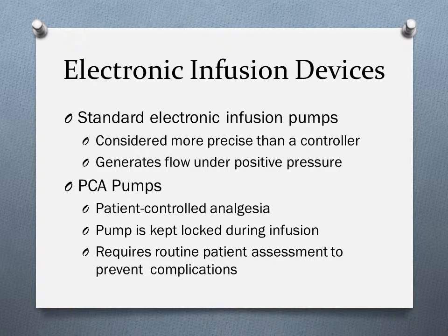Again, with PCA pumps, these are programmable for continuous infusion, bolus infusions, or both. They have a remote control mechanism where the patient can deliver a patient dose or bolus. Always follow the manufacturer's specific instructions for the use of a particular PCA pump. General information: they have a rate range of 0.1 to 30 mLs per hour. It can be increased or decreased in increments of 0.1 mLs per hour. There are programmable concentrations, and again, alarms will vary according to the manufacturer's specifications.